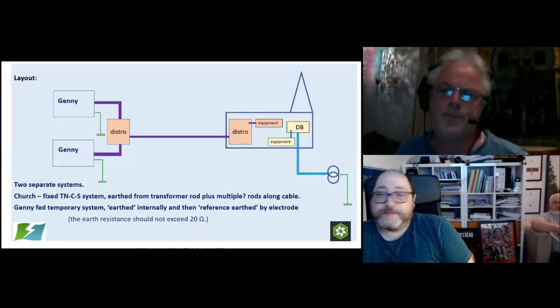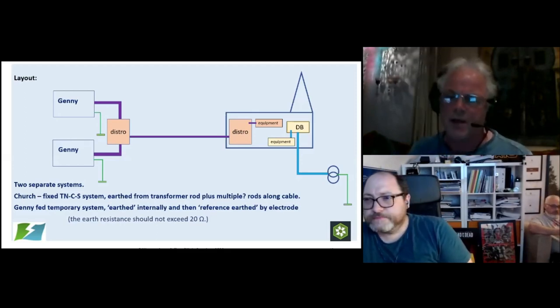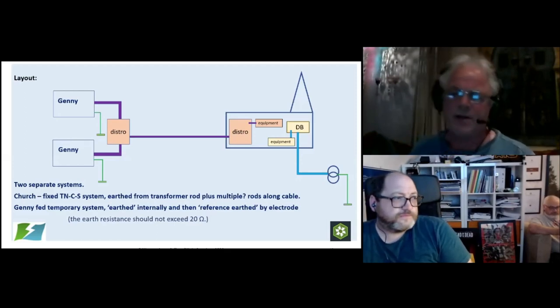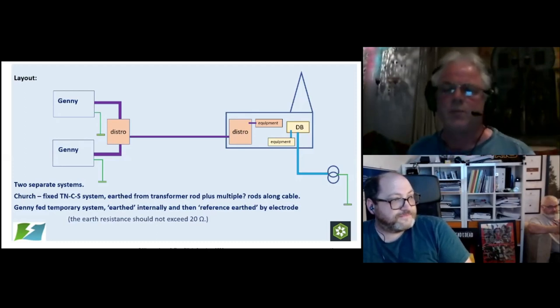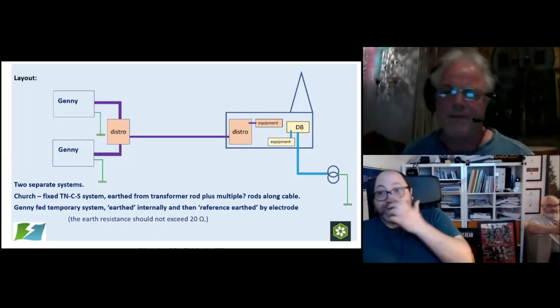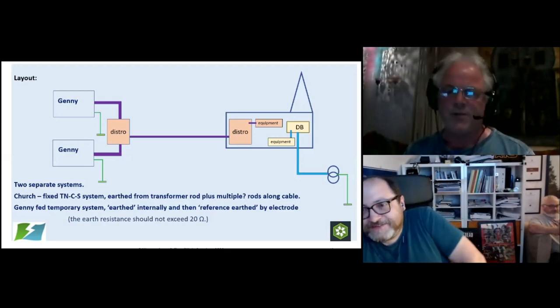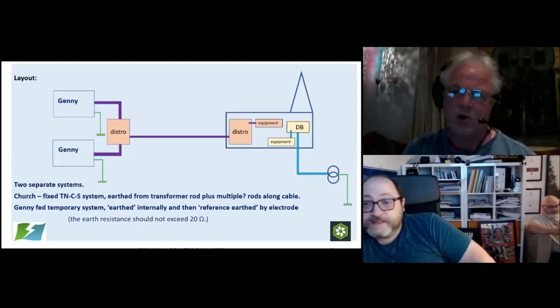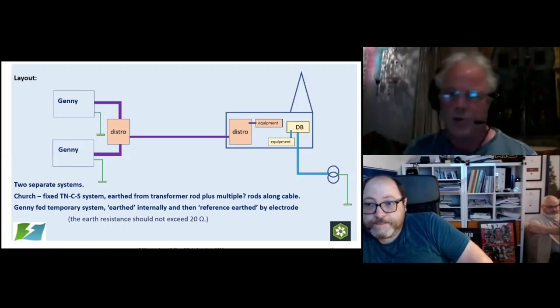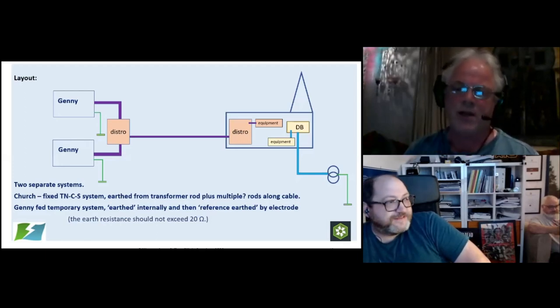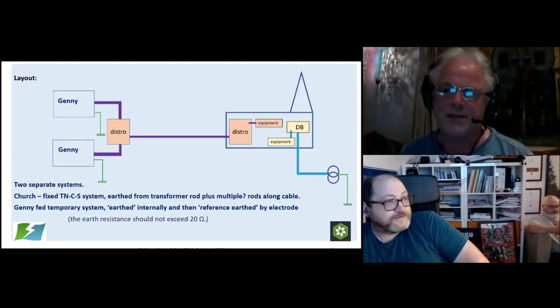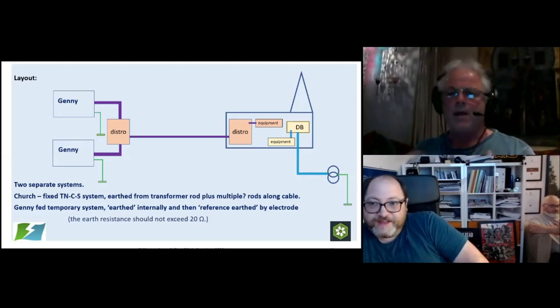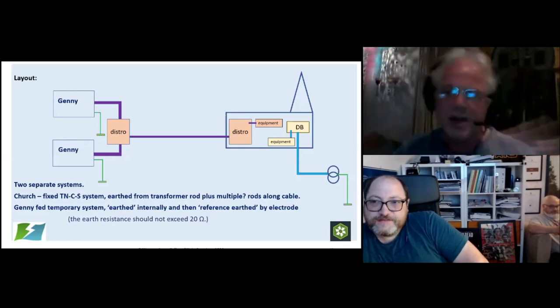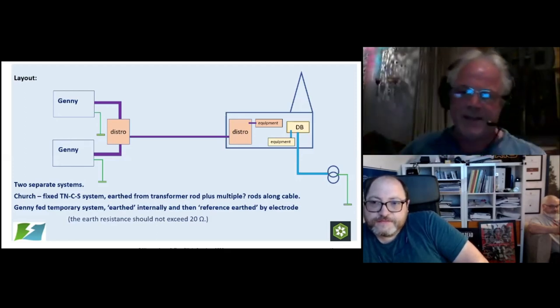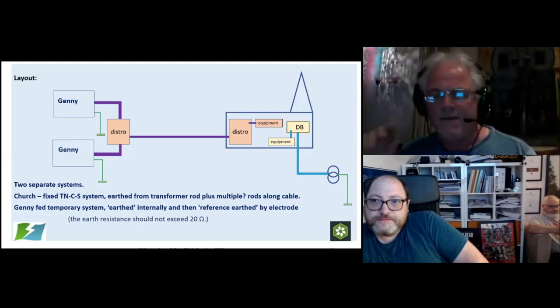Generator is TN-S. And the reason being that most generators that we use for temporary installations, because we're providing a fairly decent amount of power, will have a connection within the generator between the actual chassis of the generator and the core of the actual windings and the neutral, which is similar to the connection you get on a star connected star delta transformer. So if you swung the generator in midair, or had it elevated on a cushion of air, effectively it's still got its own earth.